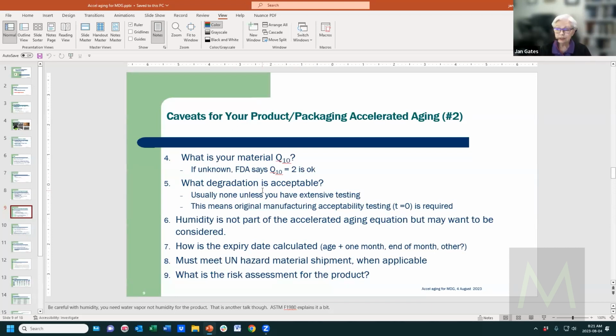And then what degradation is acceptable? Usually it's none, but sometimes you have tests and you know when your product or packaging is aging and showing changes, but they're not going to have a functional problem for you when you give it to a customer. And usually that means, in all cases, you need to know what a T = 0 or a 0 time test result is. And that's just off the manufacturing line with all your acceptability tests to show that everything looks fine.